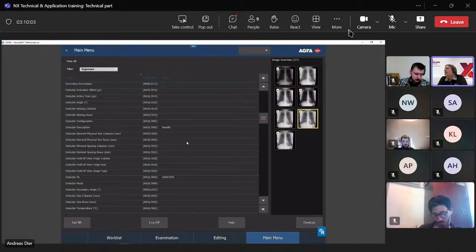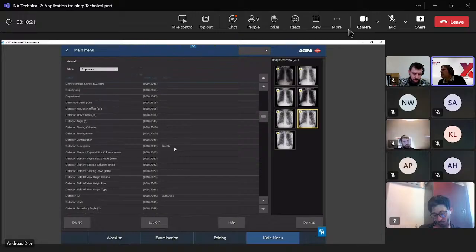The powder IPs are flexible, cheaper, and have a homogeneous sensitivity. This is the sensitivity code that we just saw before. So these are the differences between needle IPs and powder IPs. We will later also see the tool where you can import the calibration file of a needle IP, this GAIN calibration file, as it is called.